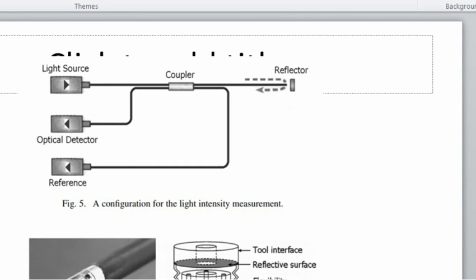The force measurement corresponded to the change in distance between a reflective surface and all three fibers arranged at 120 degree intervals. All three fibers will detect the same displacement change when only axial force is applied. If there is a radial force exerted at the instrument tip, a different displacement change will be detected on each fiber, and the resultant radial force component can be computed.